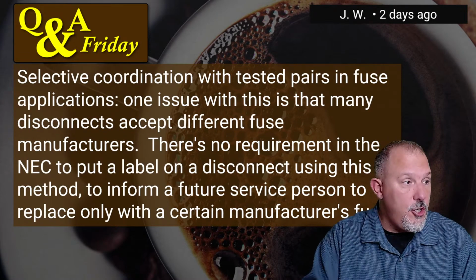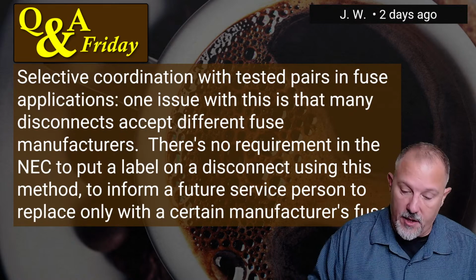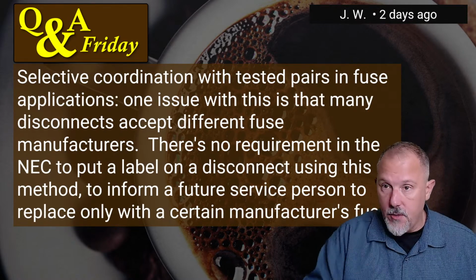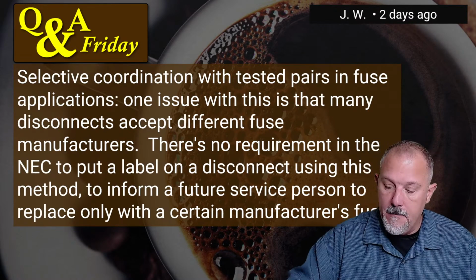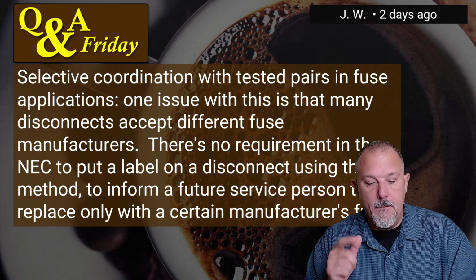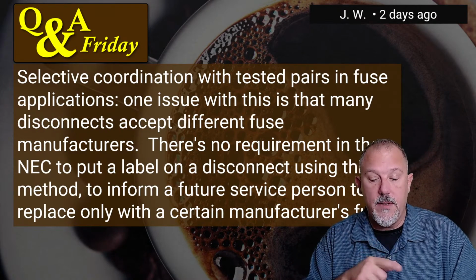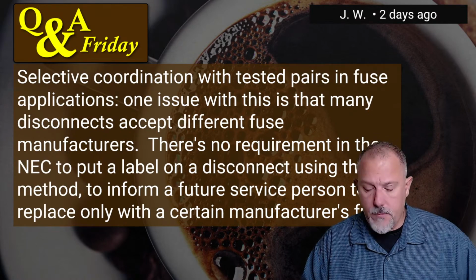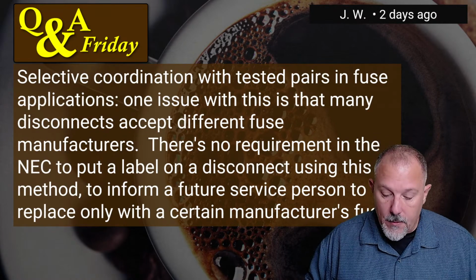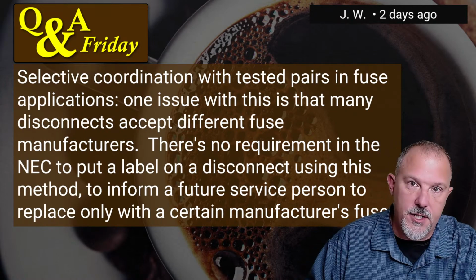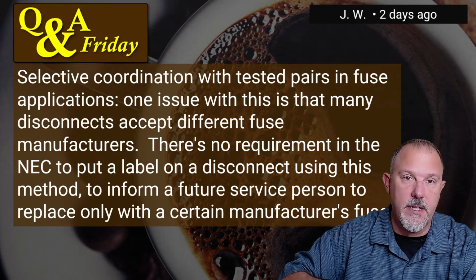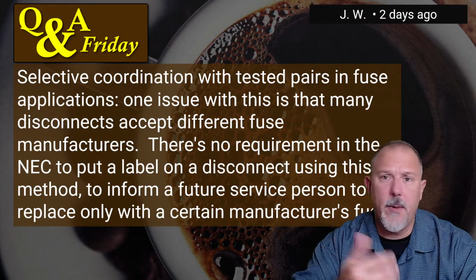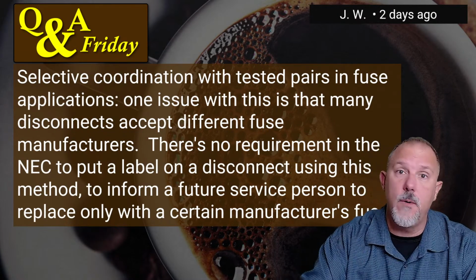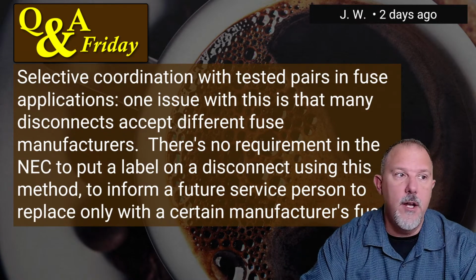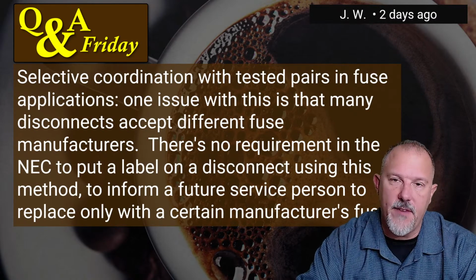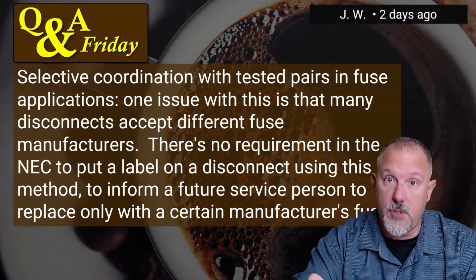So that is going to be new for the 2023 code cycle. And I would agree with you, there's nothing in the code that specifically says this, but I would argue that you probably don't even need that language because you already have the requirement. And if you make any changes in your power system, you've got to make sure you maintain the requirements. That'd be like the interrupting rating on a circuit breaker. There's nothing that says that when you replace a circuit breaker that the interrupting rating has to be higher than the available fault current. And there's no labels that say that.